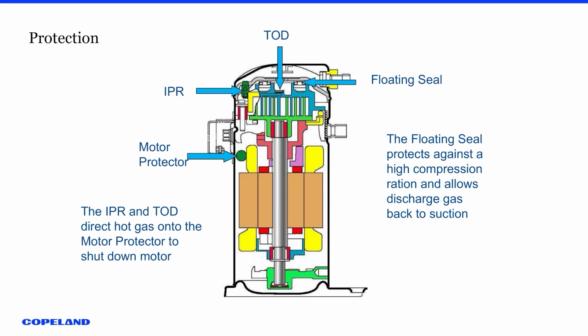As far as protection for our compressors, we have a lot of protection built in. So the floating seal is actually a protection device if the compression ratio gets too high. The TOD goes off of temperature, okay? Just a bimetal disc, if you think of a high temperature sensor for a furnace.